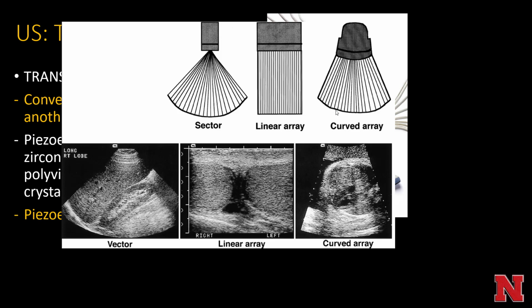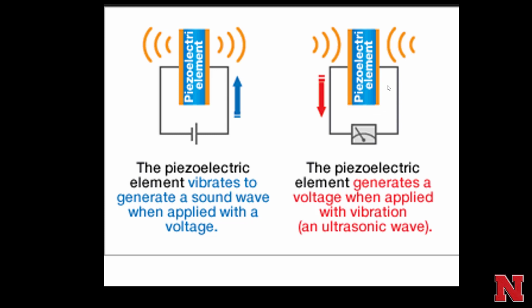You can have a sector transducer, where a single point emanates out into an array, a linear array with about 96 points, or a curved array with multiple points slightly off angle. We use these for different concepts and practical applications in imaging the body.